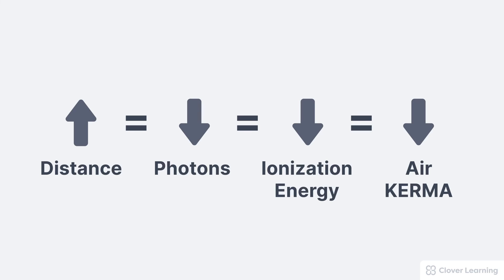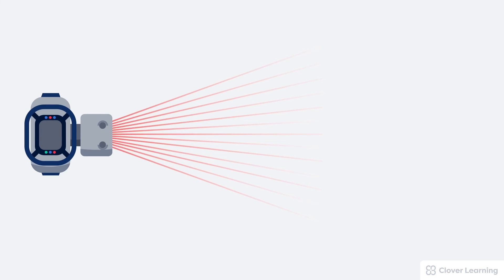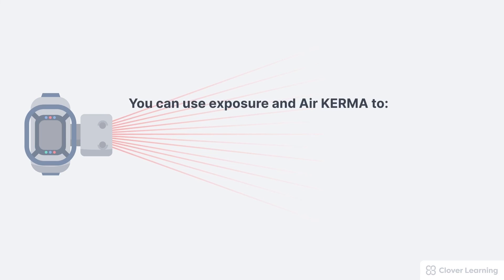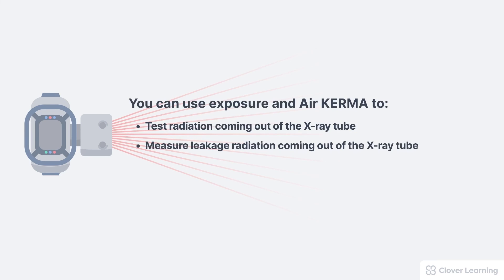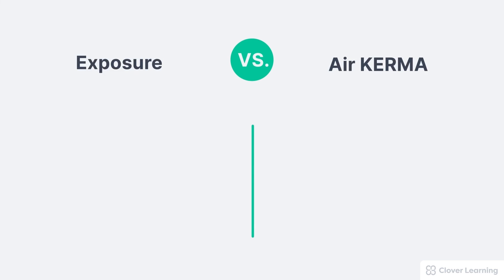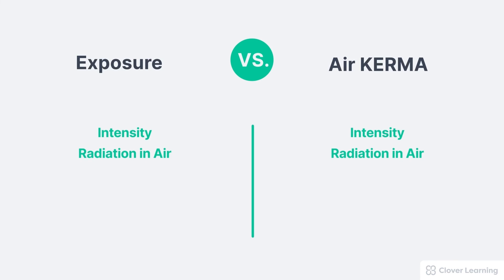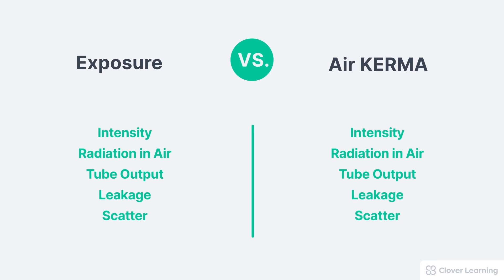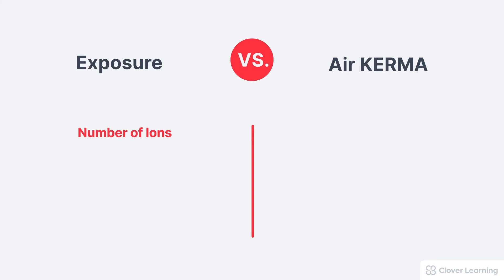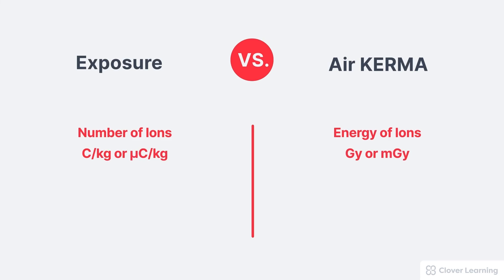So how exactly are these measurements used? Exposure and air KERMA are useful any time we're measuring radiation in air. For example, you could use them to test the radiation coming out of the x-ray tube, to measure leakage radiation, or to measure scatter radiation. Both measure intensity, both measure radiation in air, and both can be used to evaluate tube output, leakage radiation, and scatter radiation. The key difference: exposure measures only the number of ions created in air, while air KERMA measures the energy of those ions. Exposure is measured in coulombs per kilogram or microcoulombs per kilogram, while air KERMA is measured in gray, milligray, or microgray.